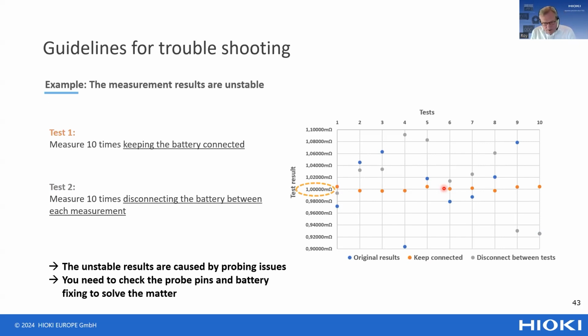It could also be that your battery is not fixed firmly in your production line and therefore can move slightly. When that happens, it will probe at a different position, and you can get poor repeatability of your measurement. By doing this kind of test step by step, you find out what might be the cause of your problem.